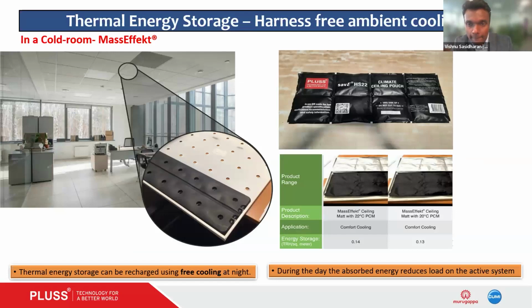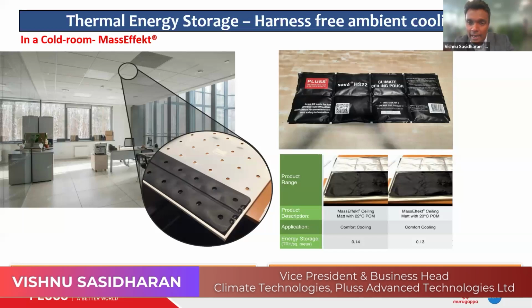This is for free cooling. This example, I think, was also covered by the previous presenter. In certain regions and countries where the ambient temperature differences are really high, depending on the time of day, phase change material plays a role to absorb the cooling when the nighttime temperatures are as much as 17 degrees Celsius, and the daytime temperature starts to rise to about 32 to 35 degrees Celsius.